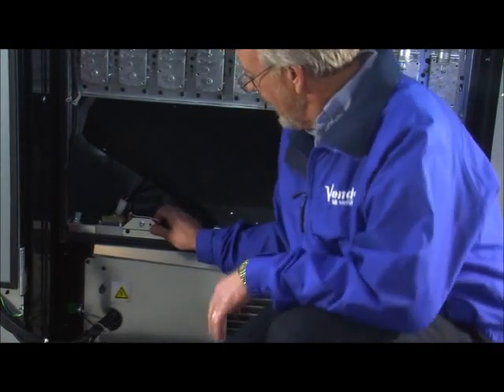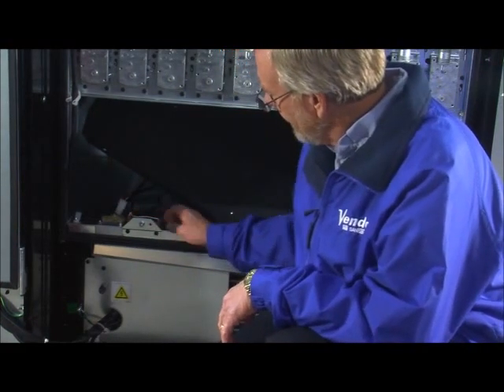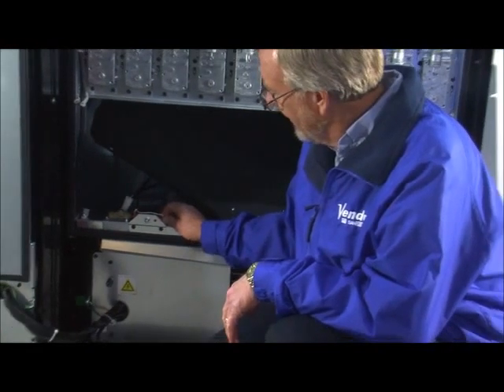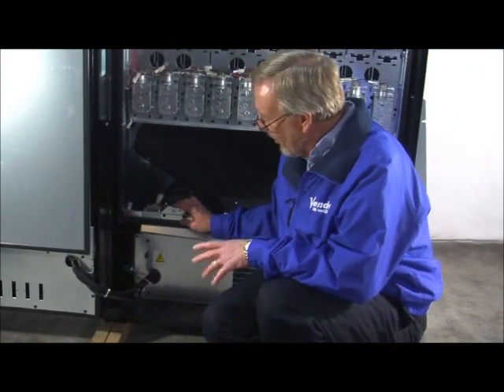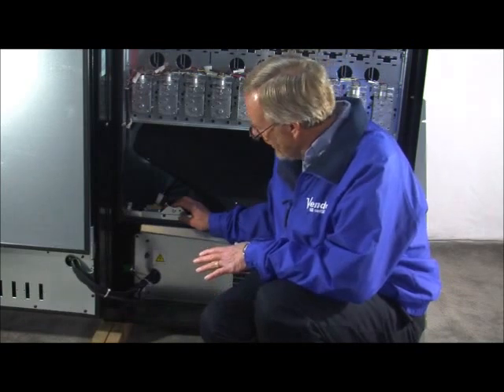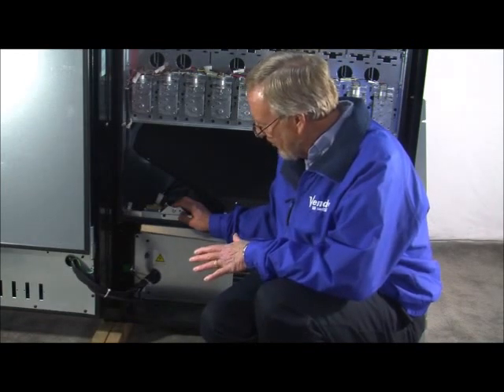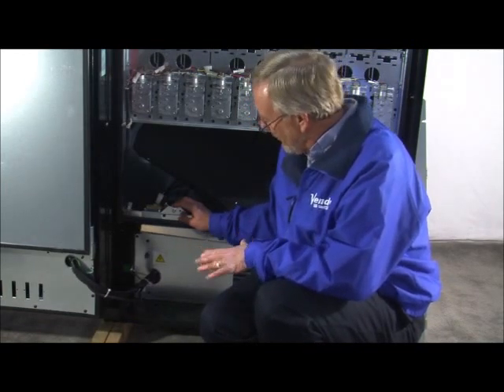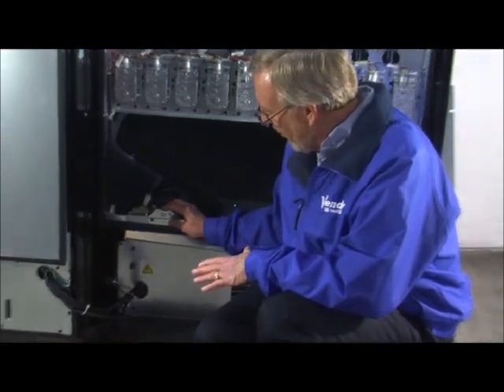While we're in this area, you have a door switch. 2 wires go to the door switch. The door switch controls the lighting, the refrigeration, and the evaporator fan. Because with Vendo, once we open the door, we turn the lights off, we turn the compressor off, and we turn the evaporator off.